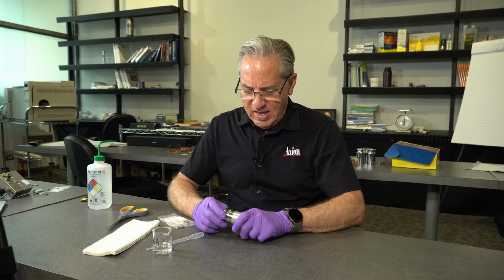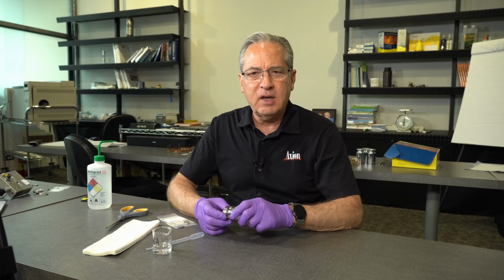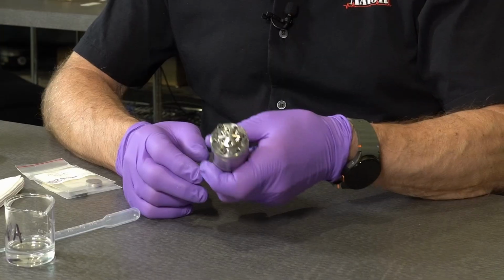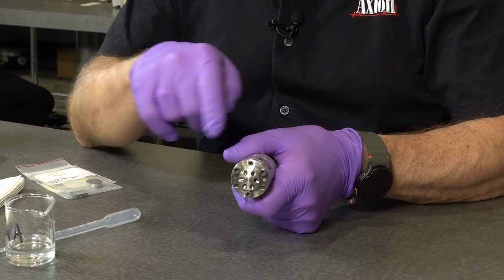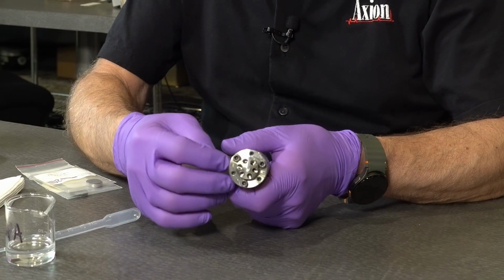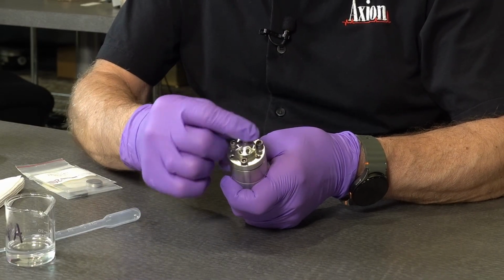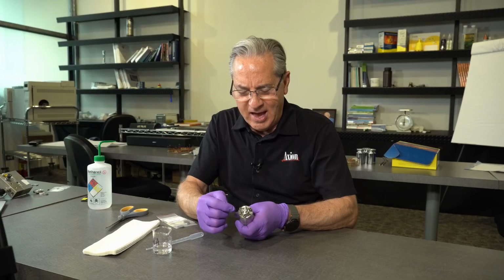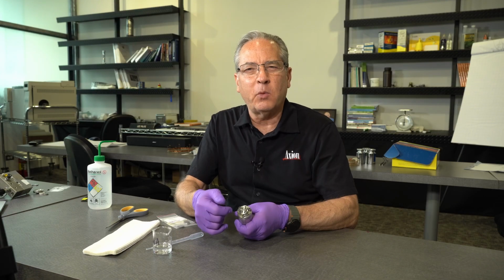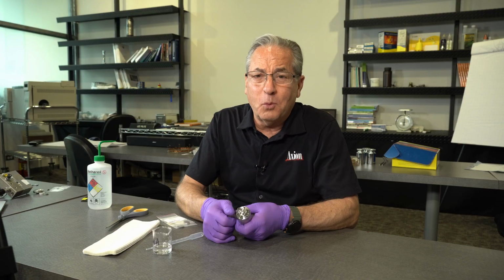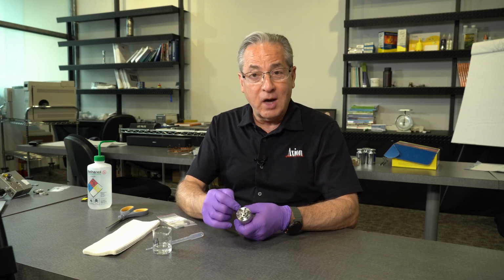So the rotor seal is inside the injection valve. So every LC injector in the world, autosampler, has some form of this valve. It's the Rheodyne 7125 or some version of it where it's called a 6-port valve. You can see 6 little holes in the back, and this is what's used to make the injection. Over time, the rotor seal is going to wear out, and when it does wear out, it's going to cause a reproducibility problem in your peak areas and your peak heights. So area and height reproducibility should be like 1 or 2%. If it's in the 10 to 20% range, then you know you've got a problem with the rotor seal.